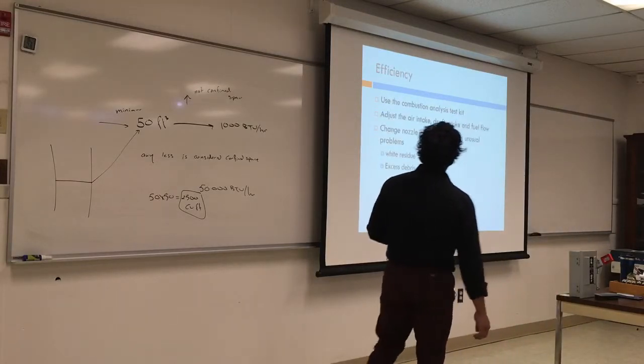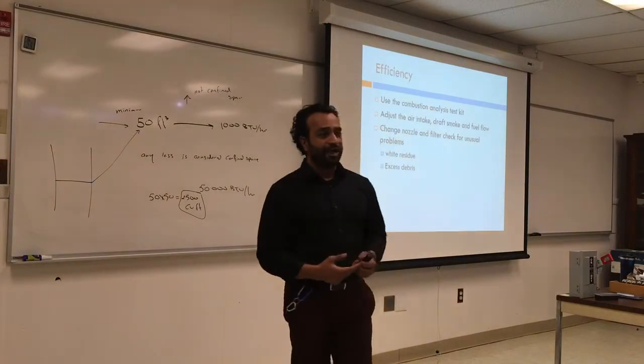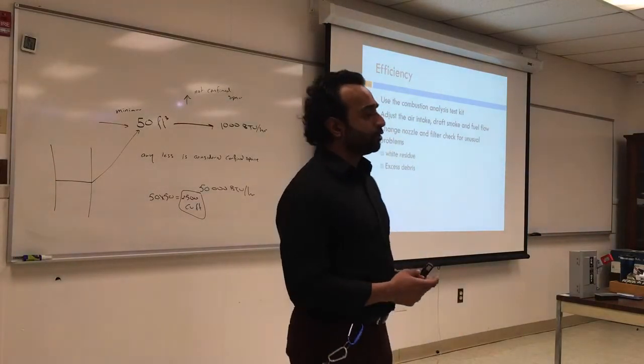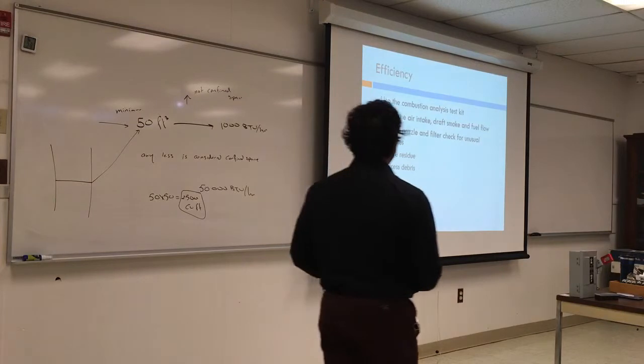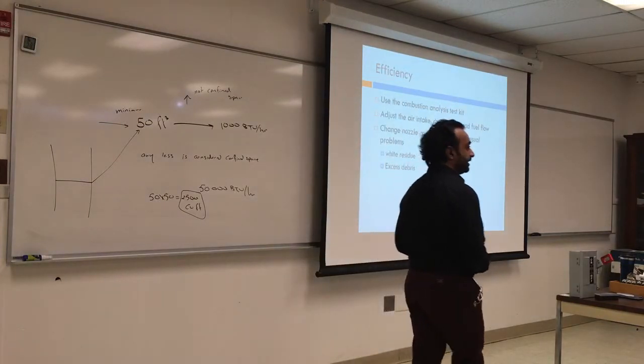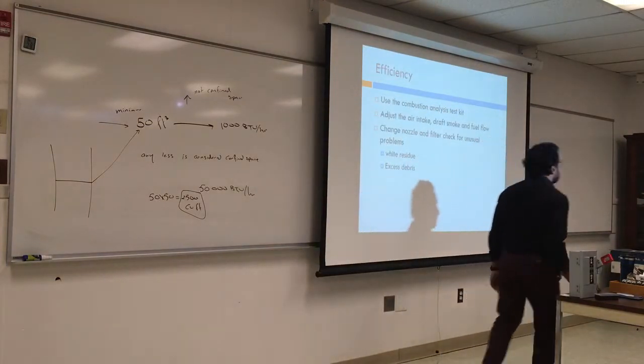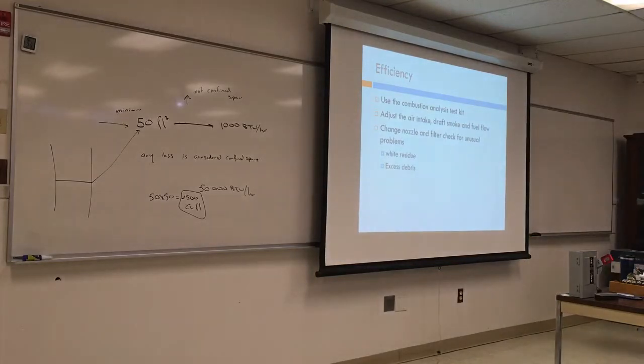Efficiency. Use a combustion analysis kit. We have 2 types of kits, either a wet kit, also called a mechanical kit. Do a combustion test, and you can use an electronic combustion test. This is an electronic combustion test. It comes with a small little printer. It does the combustion test, temperature, and efficiency, but the only thing that it doesn't do is the smoke test.